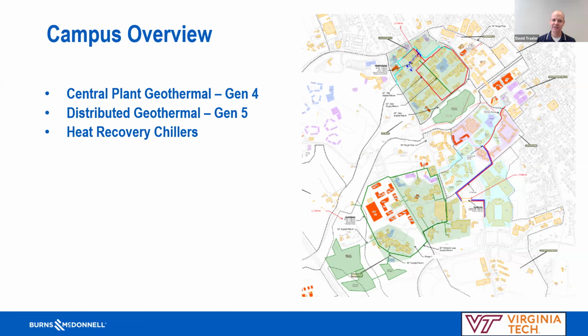We looked at a Generation 4 system, which is a central plant geothermal system distributing hot and chilled water to buildings. We also looked at a distributed geothermal system, often called an ambient loop system, or Gen 5 system, where you circulate geothermal water to buildings and each building has its own heat pumps to heat and cool. We also looked at heat recovery chiller-only systems to see how they would perform.